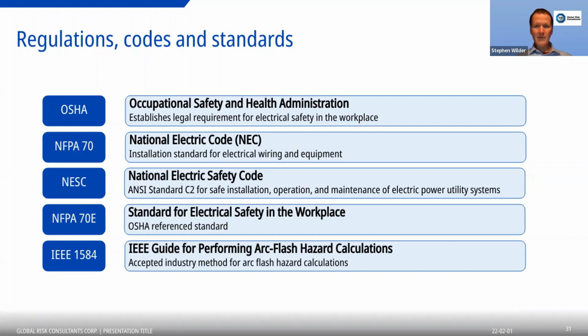But if an arc does occur and the company doesn't have arc flash labels and someone gets injured, the plaintiff's attorney is likely to argue that the company didn't provide a safe work environment because they didn't comply with codes that are so well known and so well used by anyone knowledgeable of industrial safety. So I would argue that the labels have a de facto mandate. It's also possible that an OSHA audit could result in a citation for not having an arc flash label, on the grounds that the workplace was unsafe. An argument could be made that OSHA doesn't mandate arc flash labels in accordance with 70E, but that argument would have to be made and won, which could be fairly time consuming and costly, and in my opinion would be unlikely to be successful. They can do that under the general duty clause, so there are all kinds of ways that can happen.